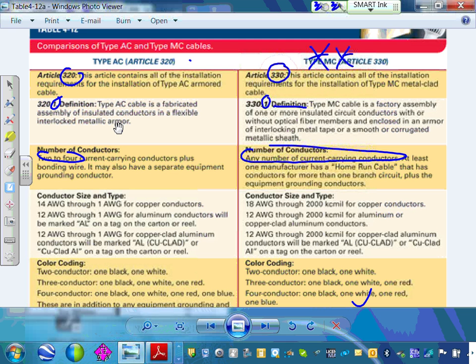Conductor size - this is my favorite. MC comes from 18 all the way to 2000 kcmil. This other one comes from 14 all the way to number 1. You see the limitation? Can you see how this guy is more superior? If you need 500 kcmil, would you find it in MC or AC cable? You see where most engineers specify MC cable - once you go higher than size 1. This, guys, is like Romex - Romex stops at number 1, and this guy also stops at number 1.